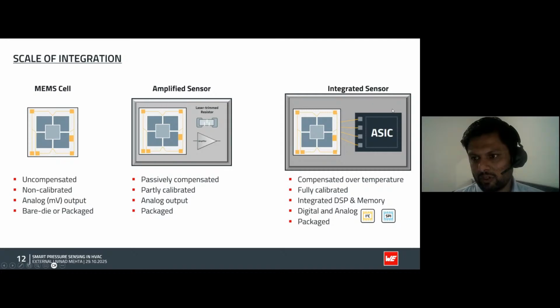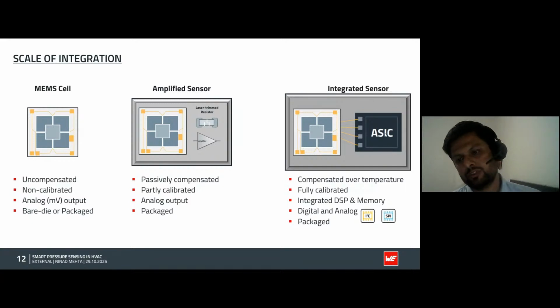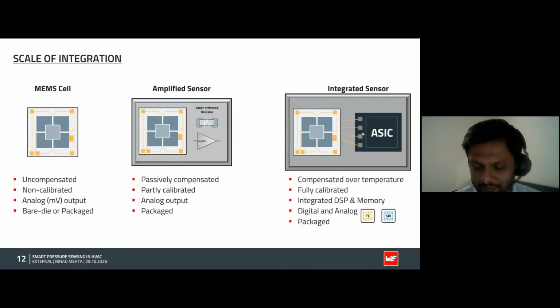The benefit of this kind of sensor is that you already have memory, and during production you can directly store calibration algorithms or parameters inside the sensor. Whenever you put the sensor into operation in the end device, this calibration algorithm is always functional. So in the end, you directly get digital output via a digital interface, I2C or SPI, and you can plug this sensor directly into your host controller and start receiving fully calibrated and fully compensated temperature and pressure values.